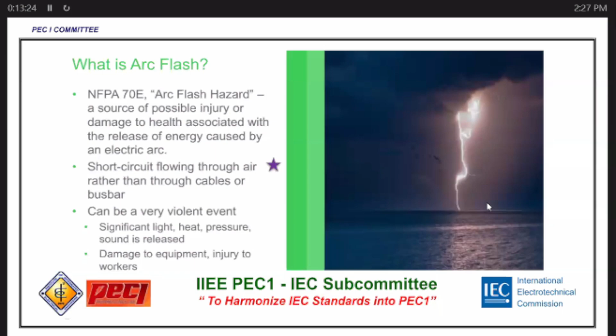Another definition, also taken from the internet, is that arc flash is a sudden discharge in electrical equipment that releases extremely high energy and temperature. This is what usually happens inside our switchgear or transformer, when there is a prolonged short circuit that is not arrested correctly by our protection or OCPD, so we get an arc flash.